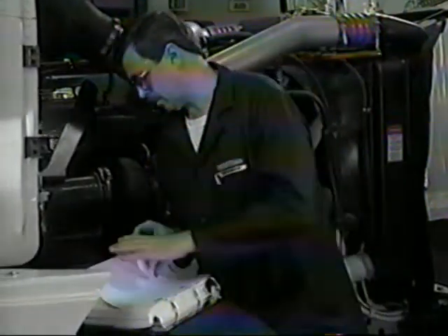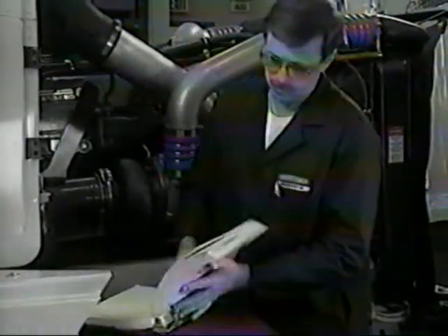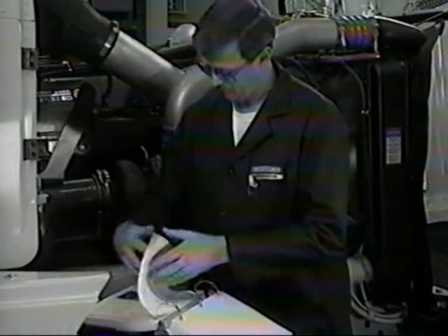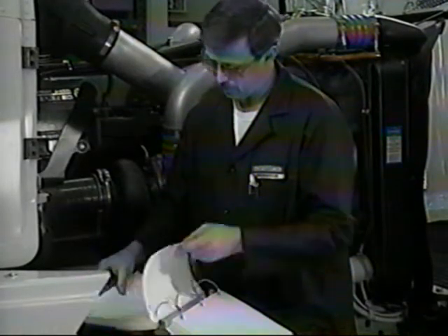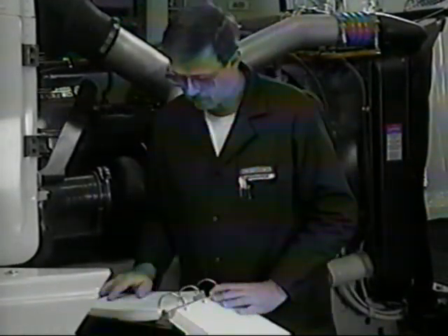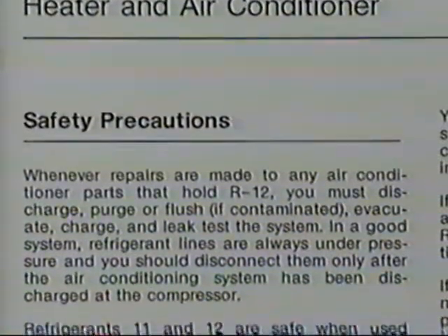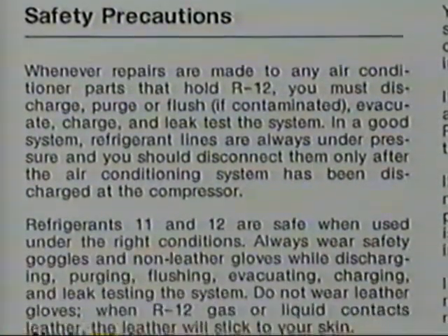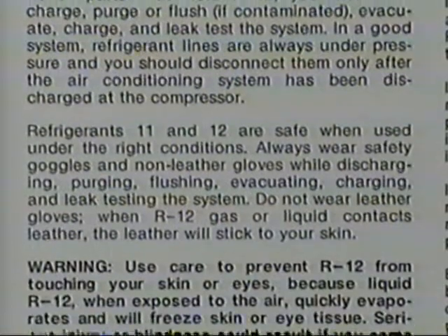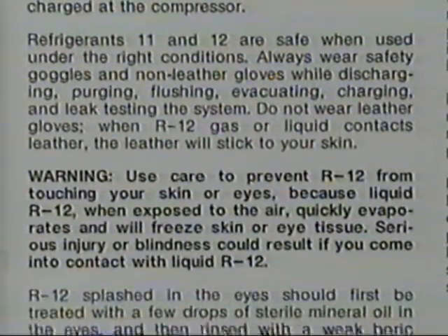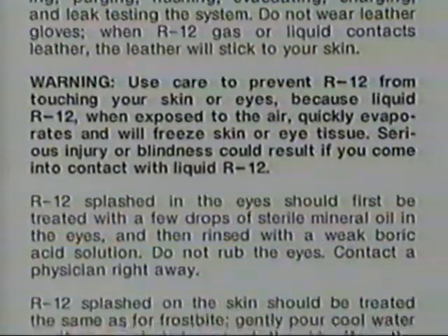Before connecting the charging station to the compressor, review the safety precautions contained in the service manual. Failure to review these safety precautions and to be aware of the dangers involved when working with refrigerant could result in serious personal injury. Safety glasses and gloves must always be worn when working with R12.